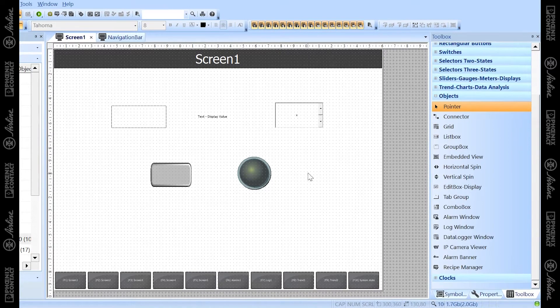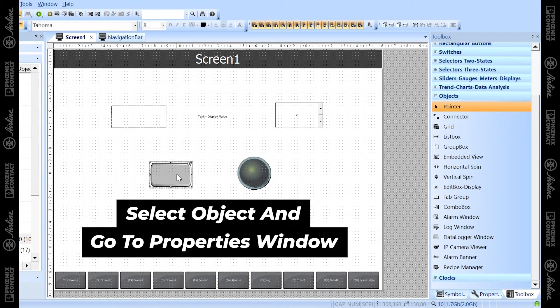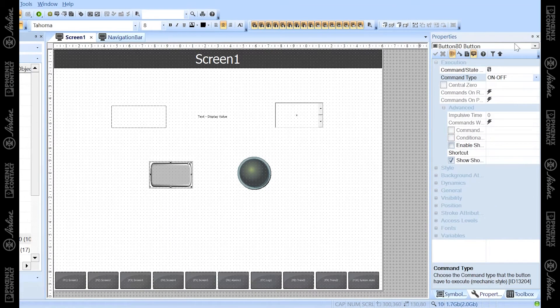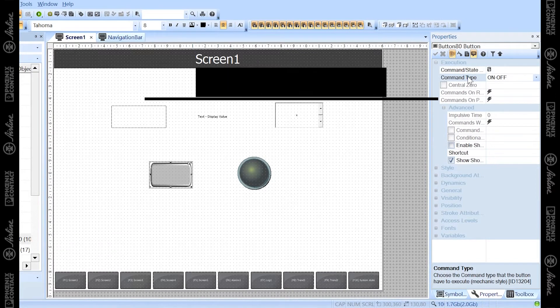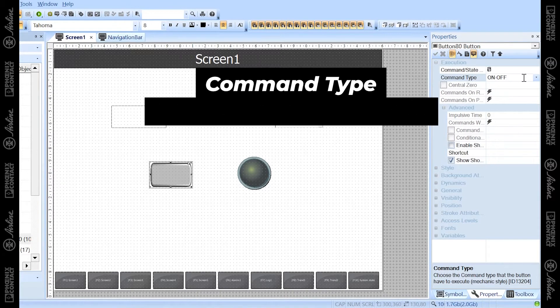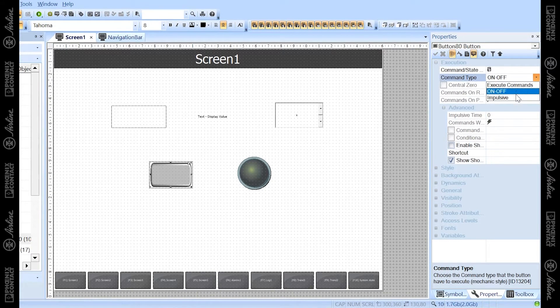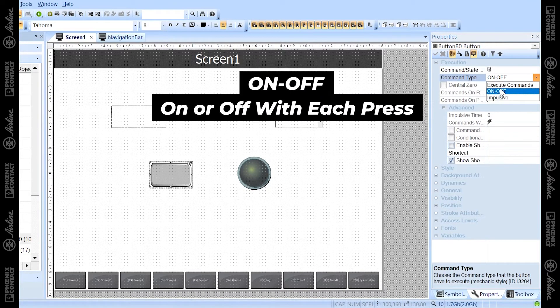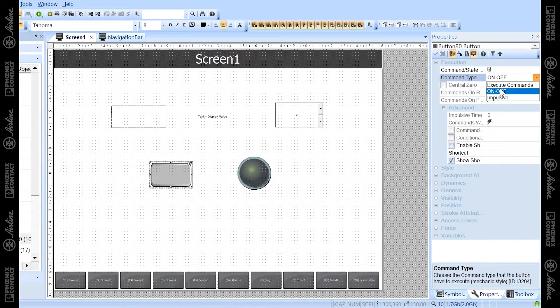Now we'll move on to button properties. These are the properties associated with objects and how they will function in your screen. For instance, if I want to edit the properties of this button, I can go to the properties window and there's a ton of different properties. I wanted to go over command type, which is how this button is going to interact. It's set to 'on off' right now — the variable associated with that button will go on and off with every press.